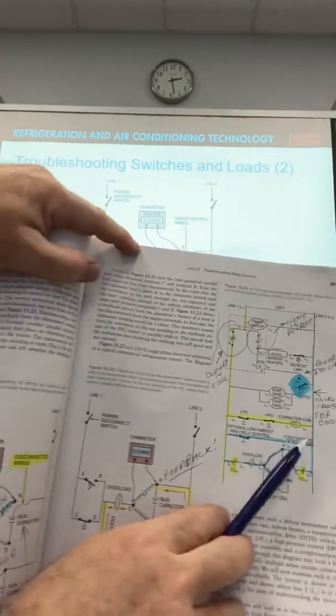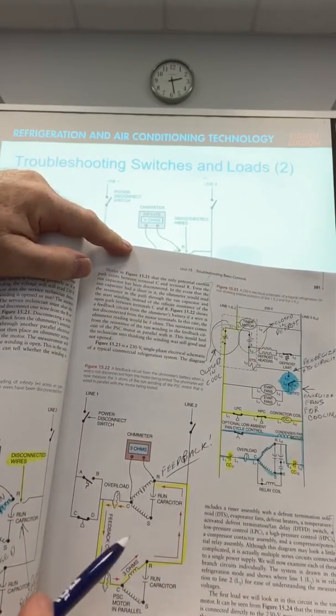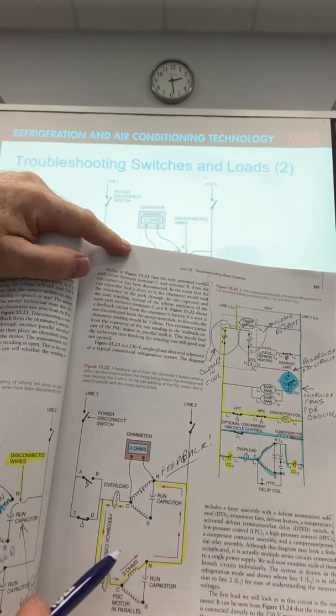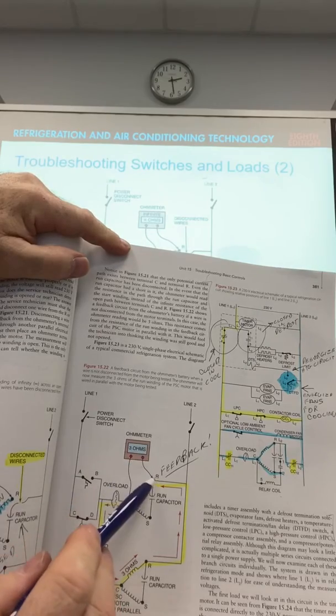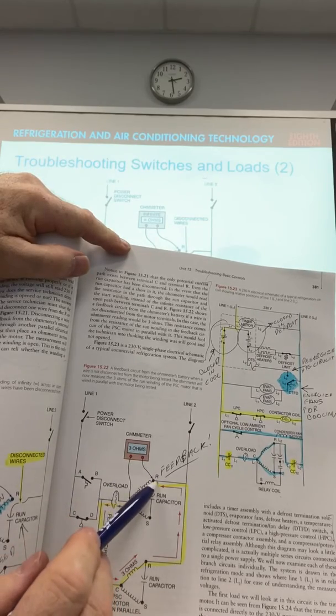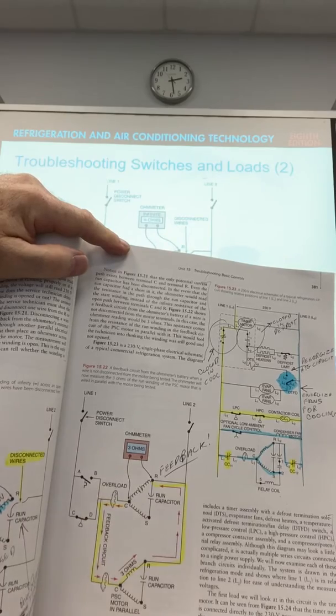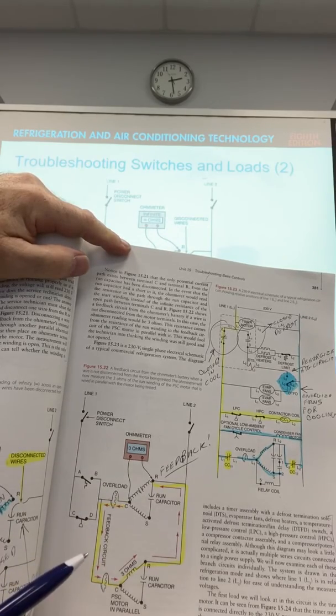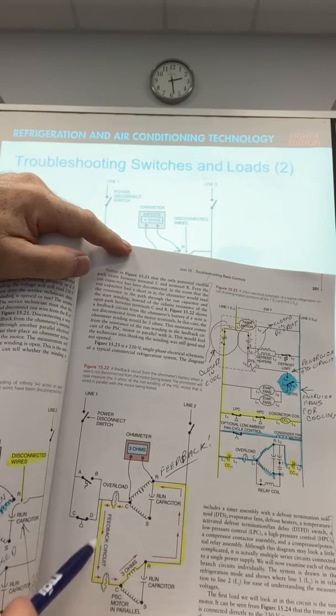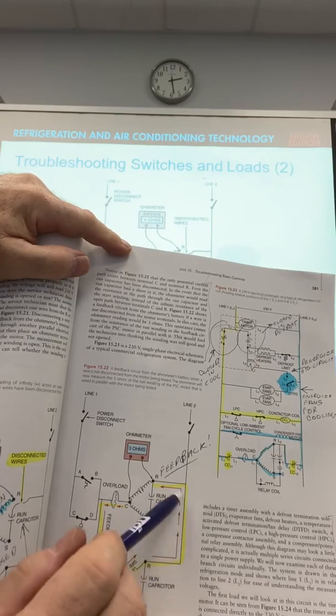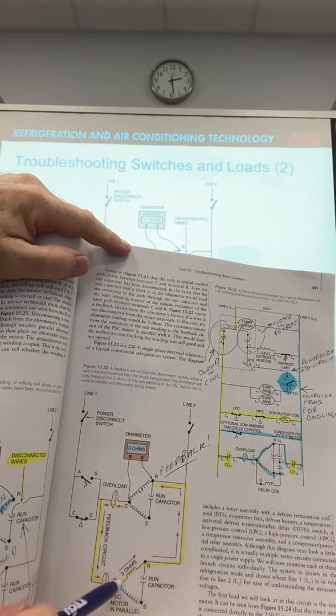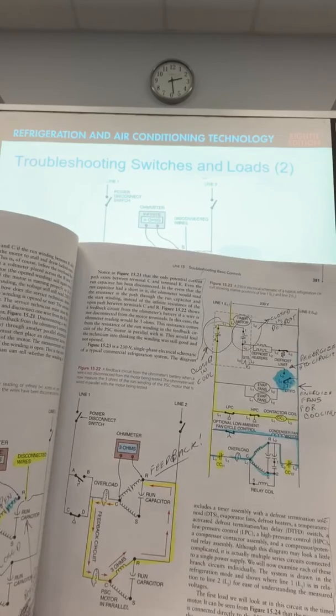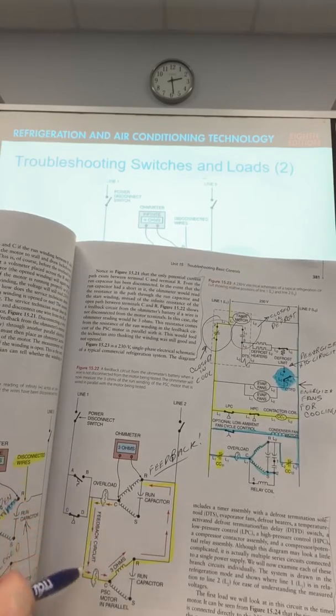Now in this one, the last one, I'll show you this when you're doing ohms. Notice we can check ohms if we don't disconnect the wires through something else. It'll backfeed. Here we're reading resistance through this winding, that's 3 ohms. So that's where we get the phrase feedback circuit, okay?